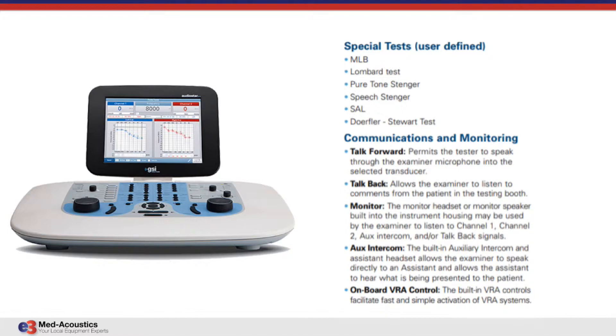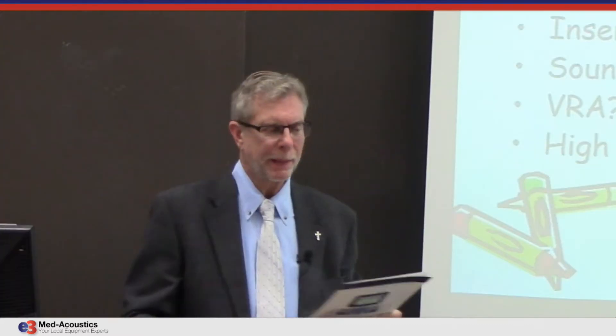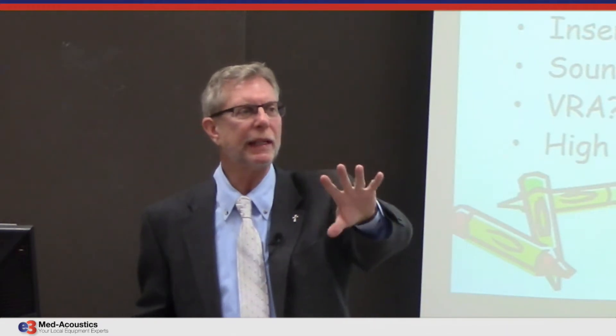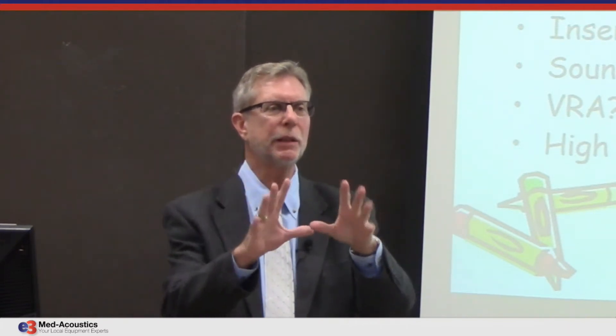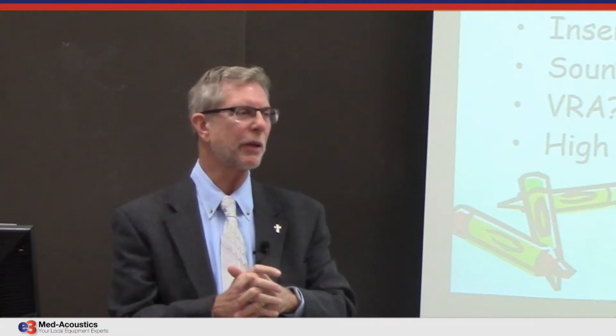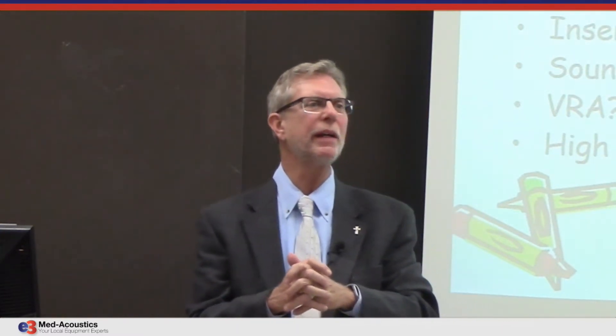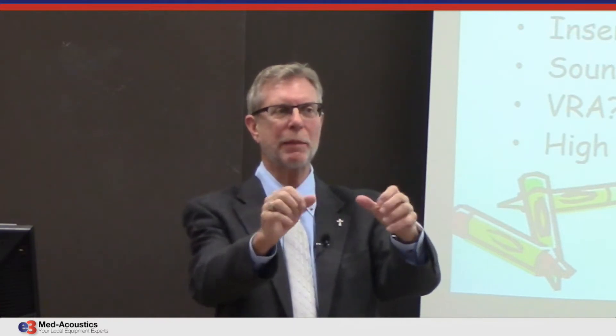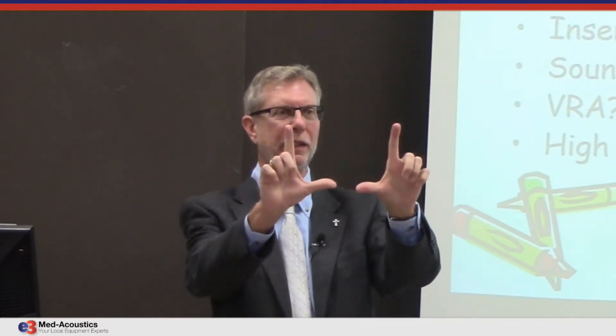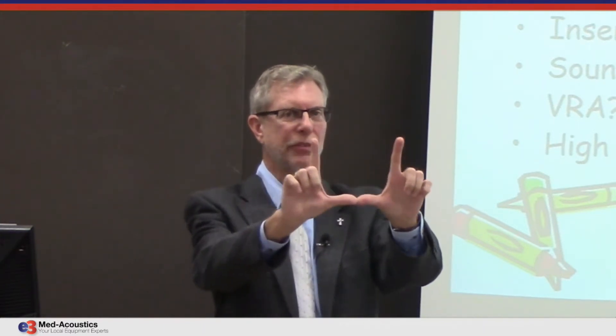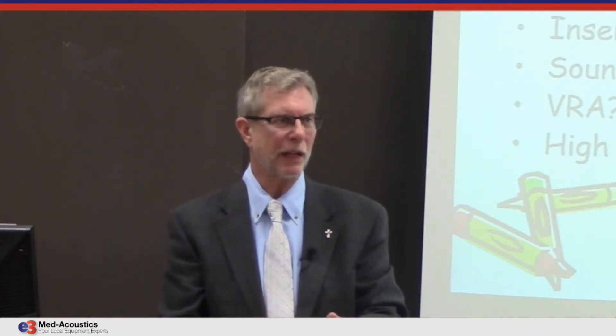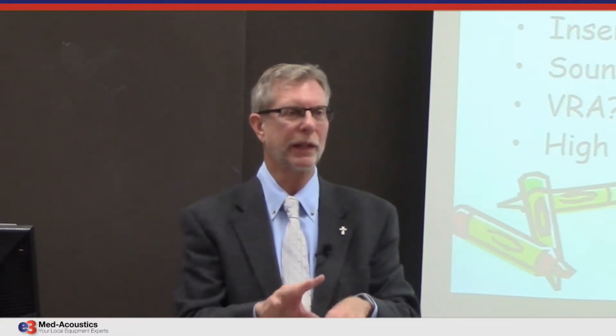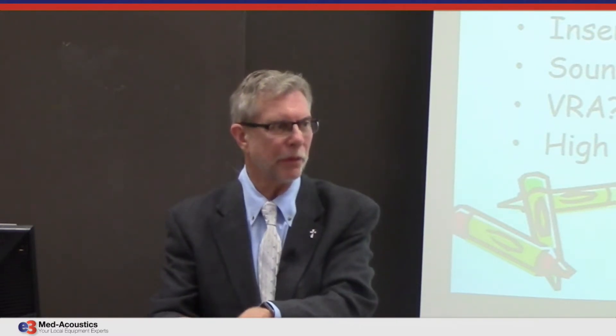Talk forward and talk back are standard. There's also the ability to put a monitor in the booth so you can operate the audiometer inside the booth for play audiometry. You could have a monitor on a swing arm showing the audiometer screen on a wall-mounted flat screen inside the booth. Then bring in a wireless mouse and keyboard, and you can operate the audiometer fully inside the booth with the patient — very helpful for play audiometry.